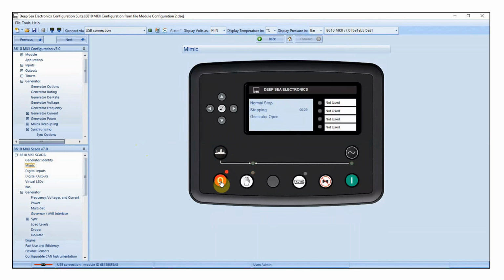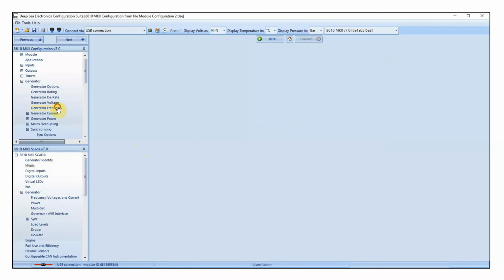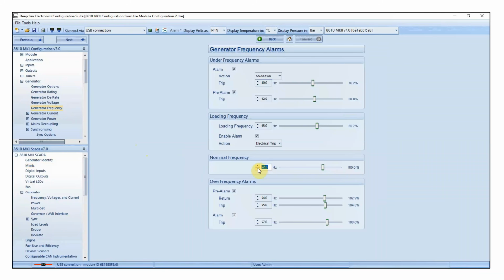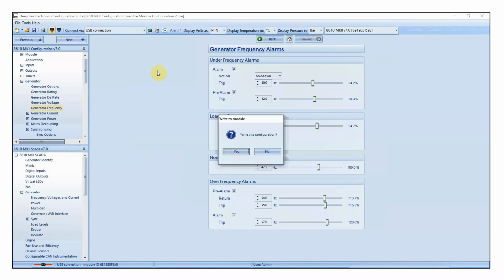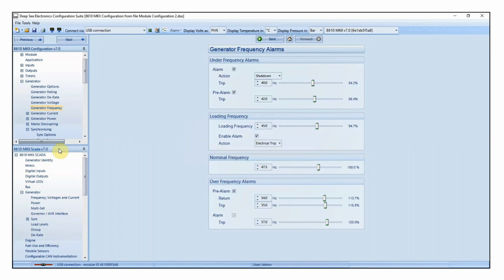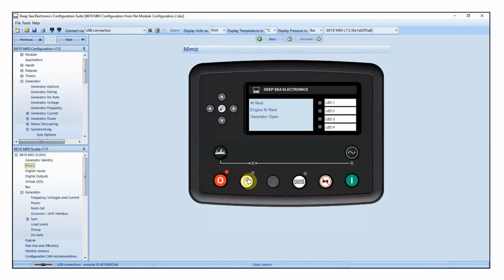I'm now going to do the exact same test, but instead of going up 2.5 Hertz, I'm actually going to go down 2.5 Hertz. In this case, that would be 47.5. And I'm going to write that back into the controller. So the procedure we're going to do this time is exactly the same. We're going to start the generator with the breaker open. It's still going to run at 50 Hertz. And then when I close the genset breaker, rather than going up to 52.5 Hertz, it's going to come down to 47.5 Hertz. And then we should still see a governor output percentage of somewhere roughly between 75 and 85%.